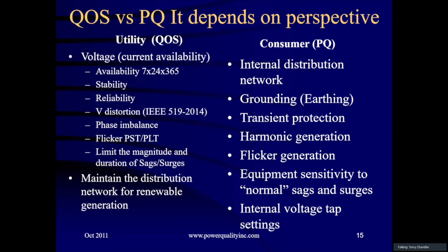Flicker generation, normally flicker is generated by steel mills, but there are other sources like motor starts. And equipment sensitivity, you know, the sags and surges and transients are normal operation of an electric utility. They cannot stop those because that's protection of the system. And so the consumer has to account for that by the equipment that he purchases or by things like you now know today as UPSs or battery backups.